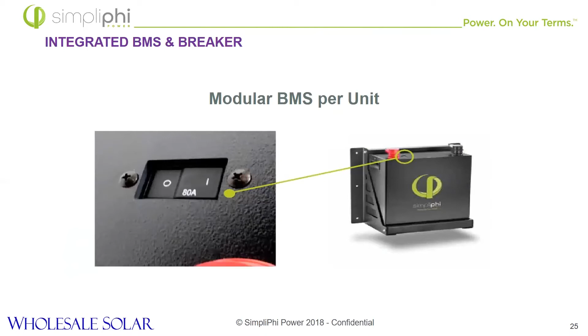You'll hear a lot of this if you've ever talked to any of us here at SimpliPhi - we all know this diagram and why it's important. This is something that maybe requires a little getting used to, it certainly was for me, in that our batteries are always wired in parallel. It's not parallel in the sense that you're going negative to negative to negative or positive to positive to positive. It's the type of parallel wiring that's shown. Note how all the leads head straight up to the positive and negative bus, and all those conductors must be of identical length and gauge.